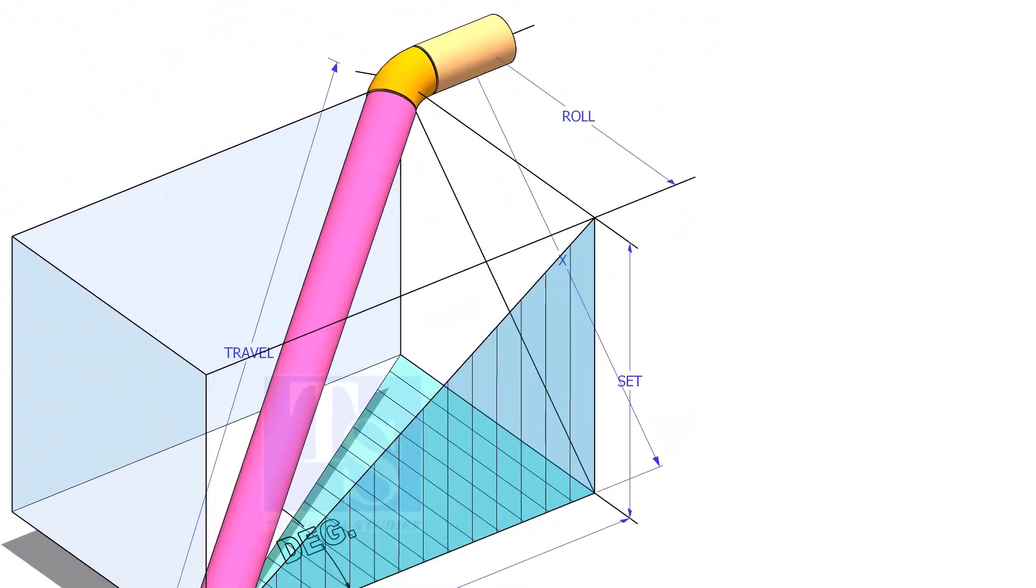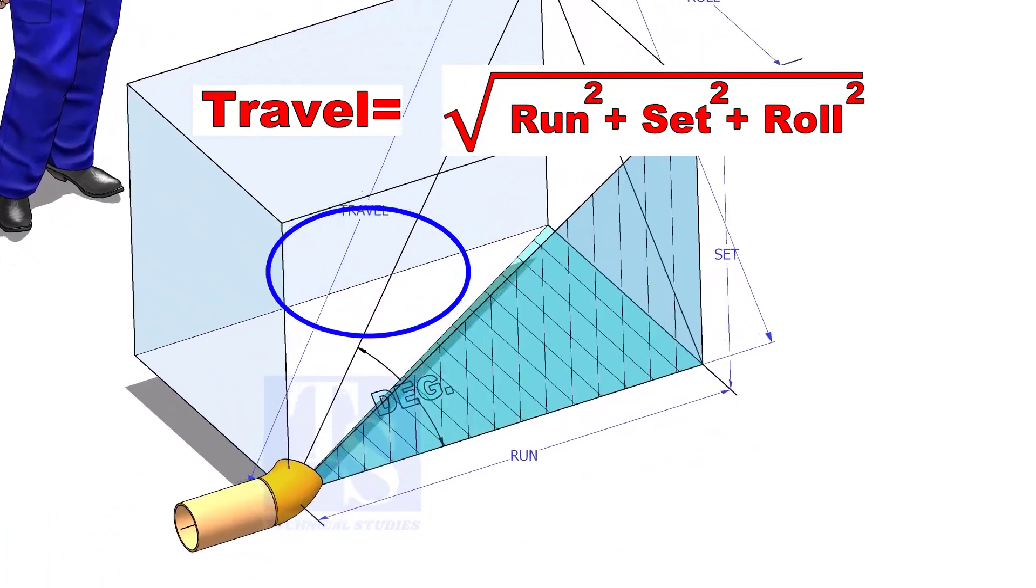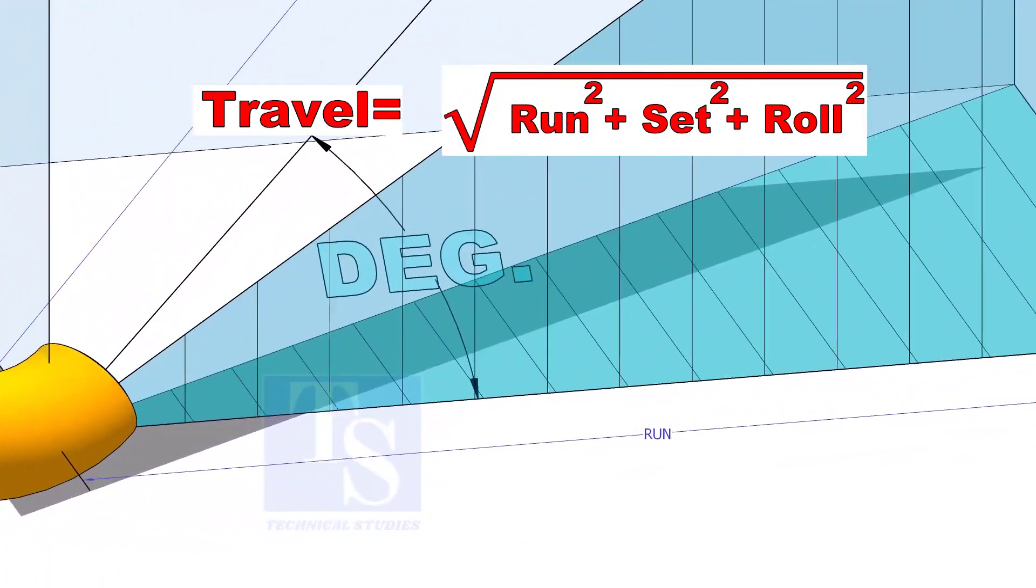The formula to calculate the travel length is the square root of run squared plus set squared plus roll squared.